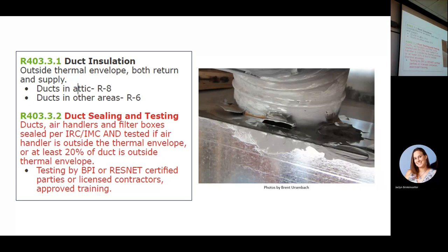how do they typically cut the holes in the duct? Do they cut it after they put up the duct, or do they cut it while it's still on the ground? I always cut them before I put it up, didn't you? You measure out where your holes are gonna be, you mark them, you cut them all out. Put your takeoffs in, put the duct on. Because it's a pain to get up there and try to cut them, and it's a pain to get up there and try to put the dovetails in.